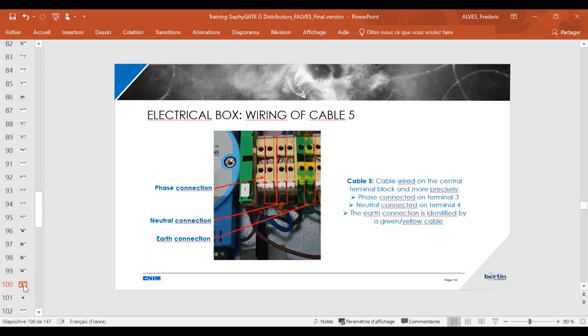Concerning cable number 5, the power supply cable for the panel PC, this is very simple also. You have to connect the phase on terminal 3, the neutral on terminal 4, same as the 230 volt cable. The earth connection is of course on the center of the terminal blocks, identified by a green-yellow cable.